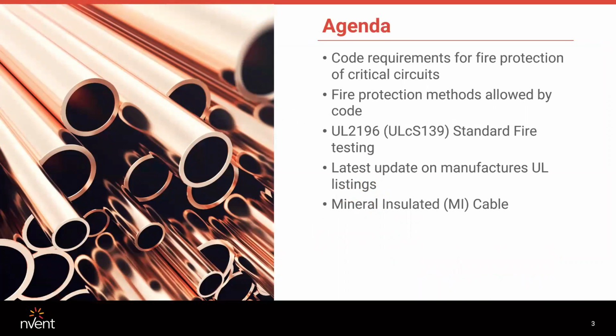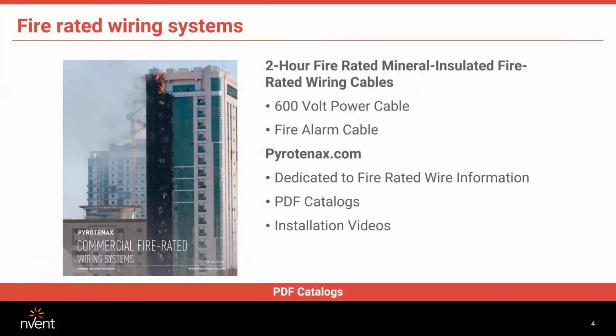A little bit about what we're going to cover today: the code requirements, various fire protection methods. We're going to talk about UL testing, the latest updates from UL, and of course we're going to talk about MI cable. Basically, MI cable is a 2-hour fire-rated mineral insulated cable. It's a 600-volt cable. We also manufacture fire alarm cable. We've got our own website, pyrotenax.com, which has pretty much all the info you need to specify and work with our product.